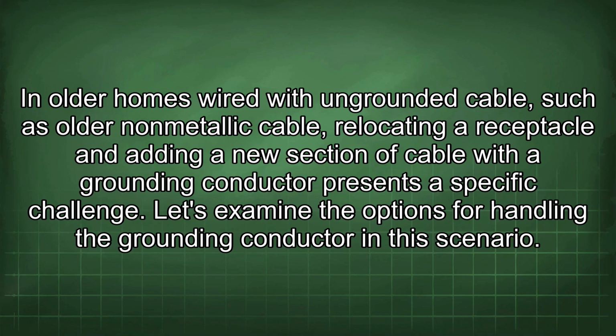In older homes wired with ungrounded cable, such as older non-metallic cable, relocating a receptacle and adding a new section of cable with a grounding conductor presents a specific challenge. Let's examine the options for handling the grounding conductor in this scenario.